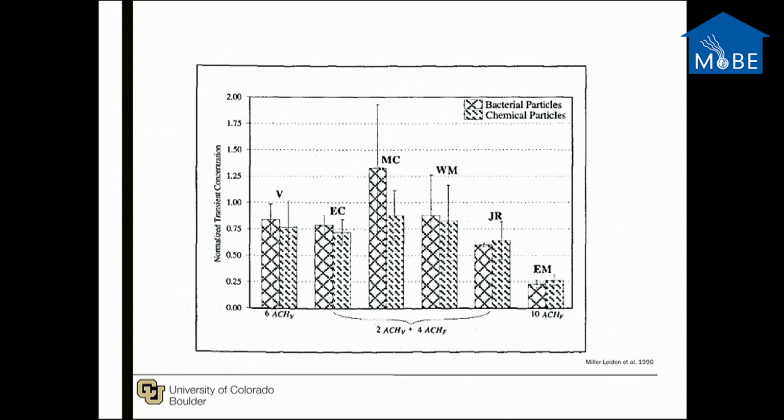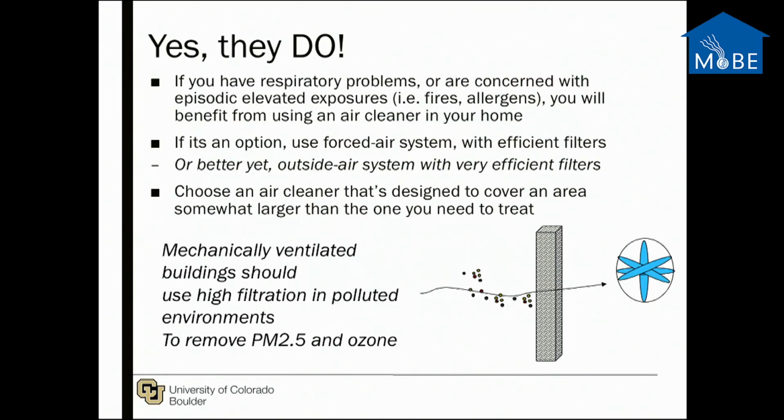And this is because the major factor affecting particle capture by a filter is its aerodynamic diameter, determined by the particle density, shape, and physical diameter. So that, in fact, when you see an airborne microbe, it's just as if it was a regular particle, and we'll treat it the same way as an environmental engineer.